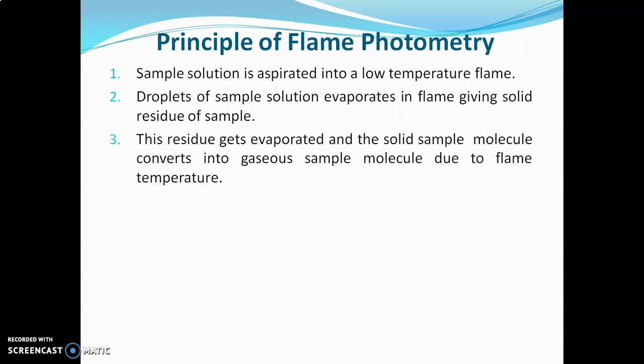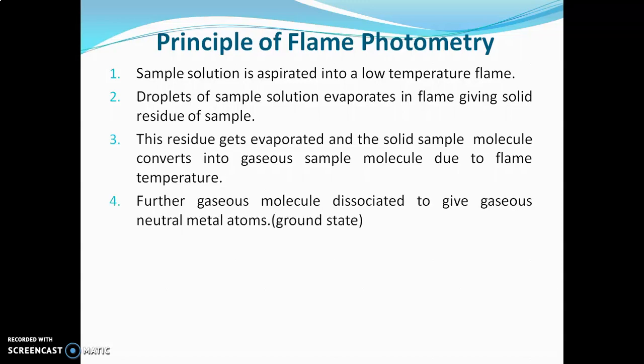Now we will go through the principle in detail, step by step. First, the sample solution is aspirated into a low-temperature flame. Droplets of this sample solution get evaporated in the flame, giving rise to a solid residue of the sample. This solid residue then gets evaporated, and the solid sample molecules convert into gaseous sample molecules due to the flame temperature.